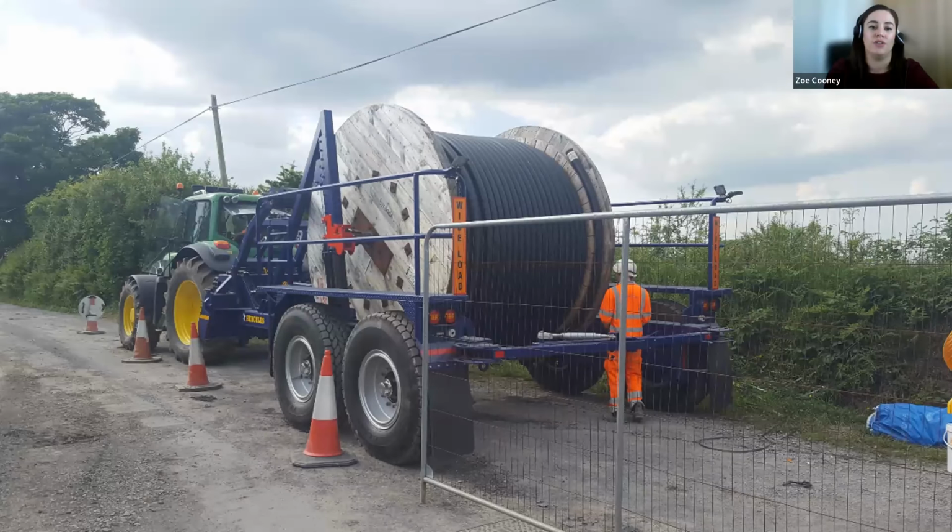This is a photograph of the cable on the spool. This will be part of the grid connection, the main grid connection. Generally, in the ground, in the ducting, whenever you're designing your main grid connection, there will be joint bays every 800 meters to 1 kilometer. It'll depend exactly on the distance of the joint bays depending on the design. But for example, if you have a 10-kilometer run of cable, you'll be expecting around 11 to 12 joint bays.